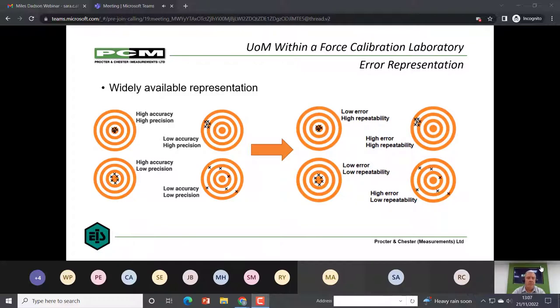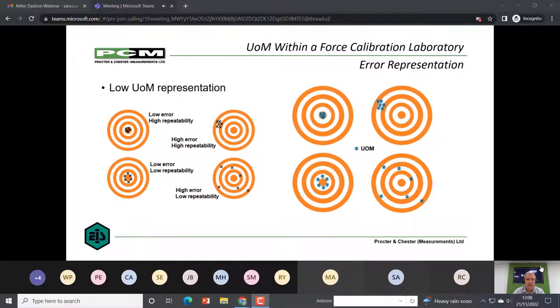So first of all, if we change over from high accuracy, high precision to low error, high repeatability, that gives you more understanding of the terminology that is used within calibration facilities. So if we now look at uncertainties on those, there's always going to be a level of uncertainty associated with a measurement. So here on the right hand side, if we have a representation of a low uncertainty prescribed by the blue box or blue circle, you can see now if we take the actual measured value away, there is going to be some level of grouping or not grouping.